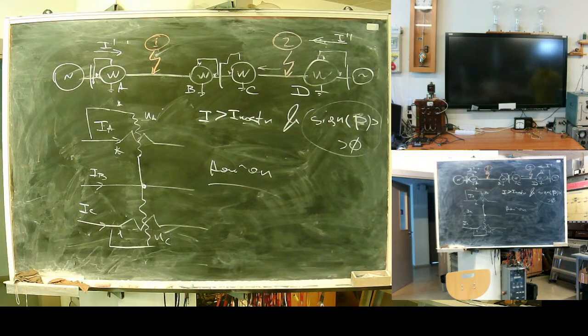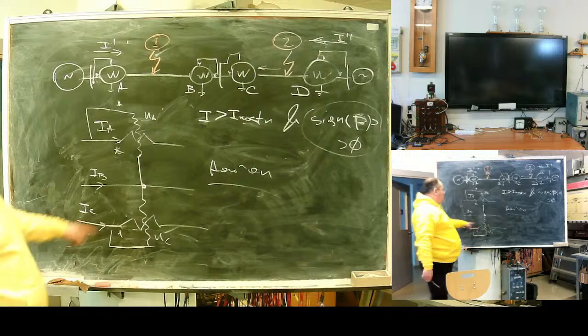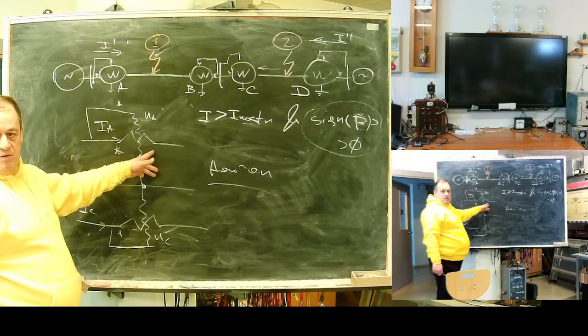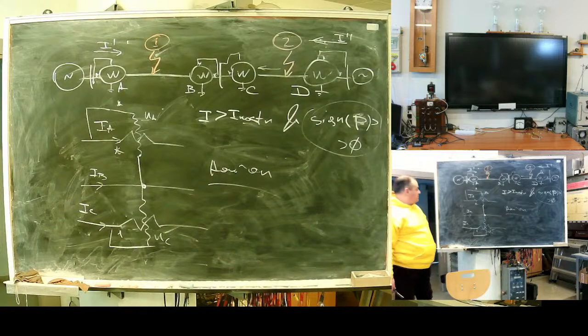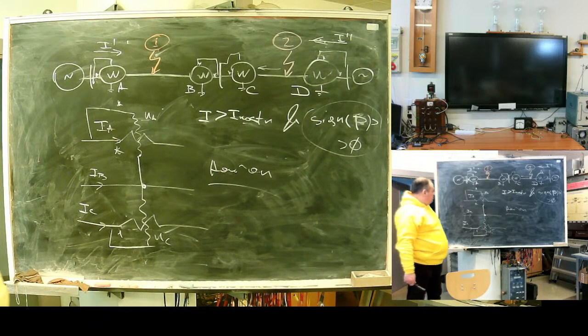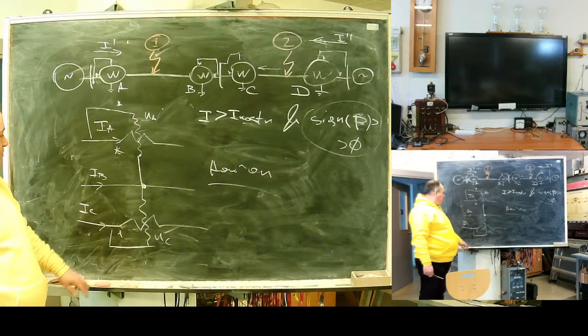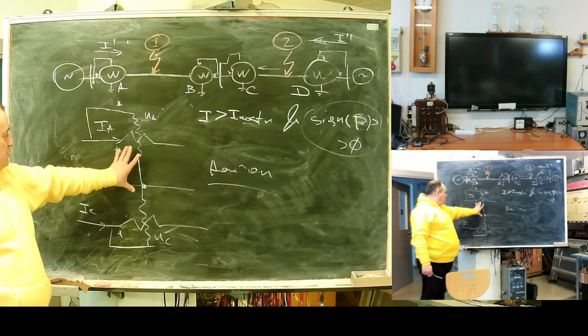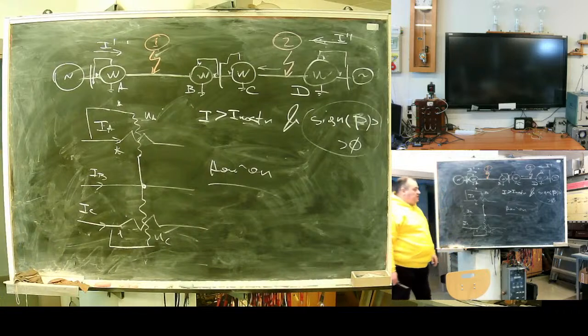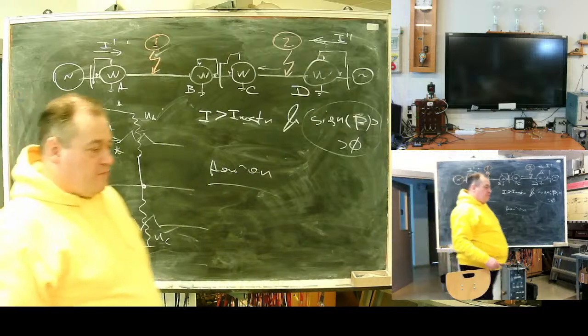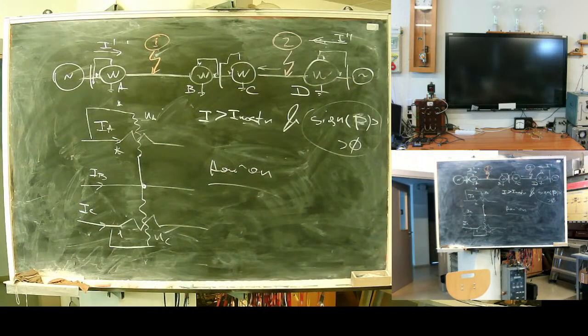What kind of fault can involve A phase? A phase can be AB or AC, yeah? In case of AB, this voltage will be 0. Relay will not operate. AC, we will get this voltage. What will happen? These two voltages collapse. Problem with meters: voltage disappears.